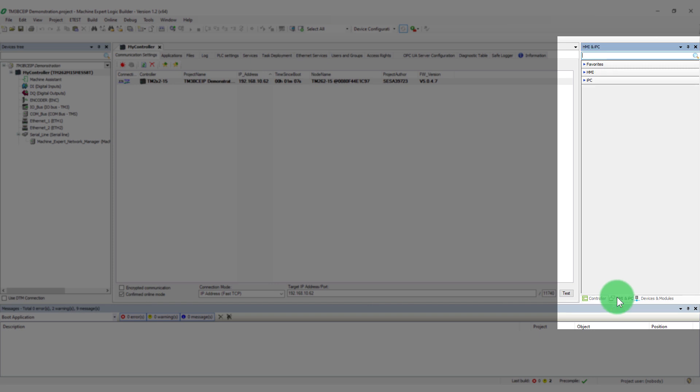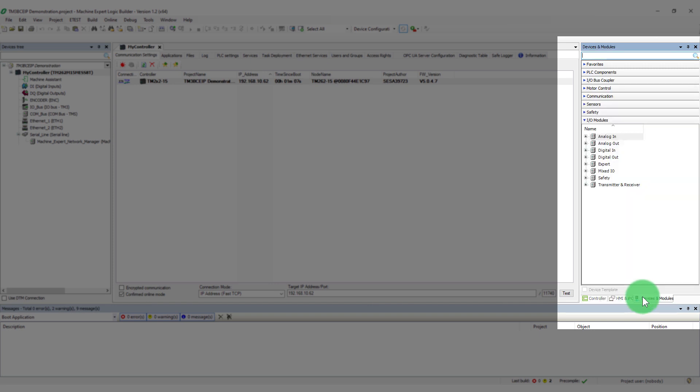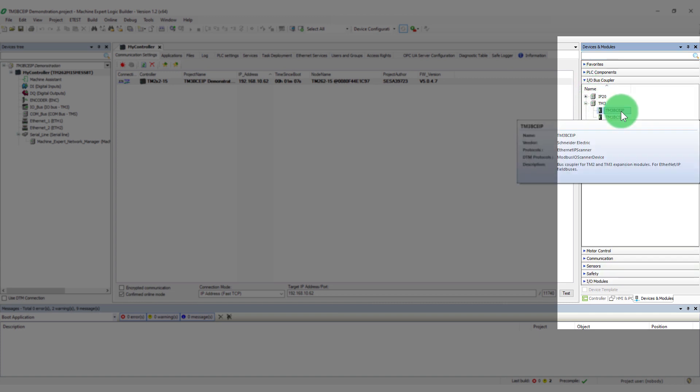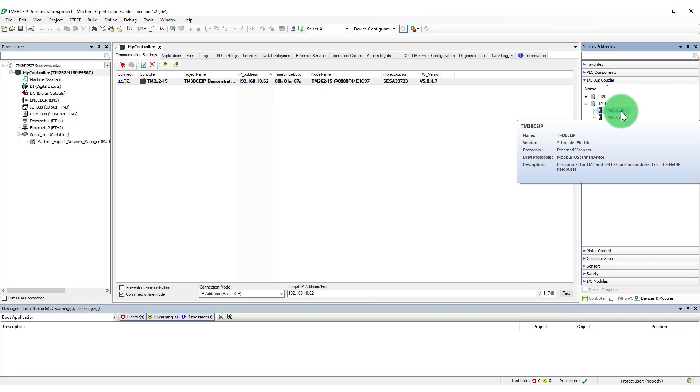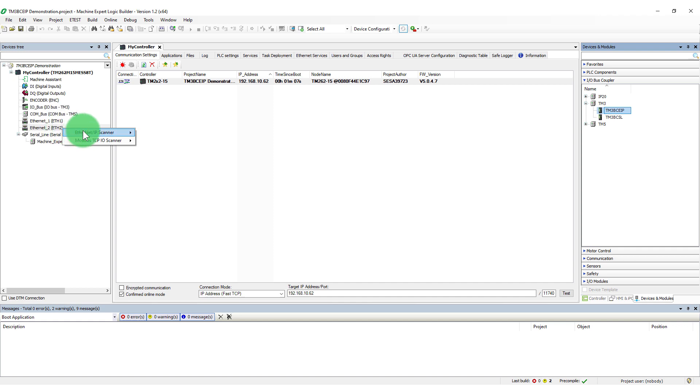Select Devices and Modules tab, I.O. bus coupler. Select the correct bus coupler. Drag the icon to the PLC Ethernet adapter. Choose Ethernet IP or Modbus TCP according to your equipment needs.